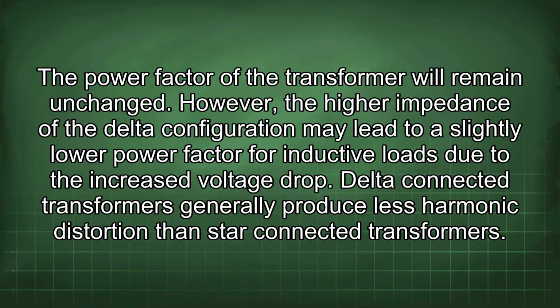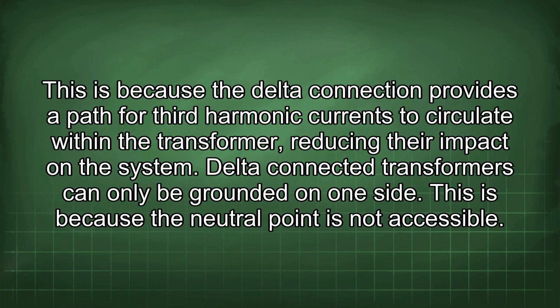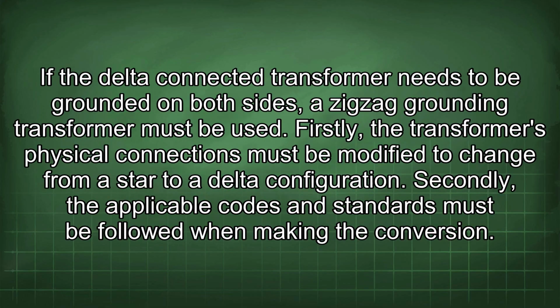Delta-connected transformers generally produce less harmonic distortion than star-connected transformers. This is because the delta connection provides a path for third harmonic currents to circulate within the transformer, reducing their impact on the system. Delta-connected transformers can only be grounded on one side. This is because the neutral point is not accessible. If the delta-connected transformer needs to be grounded on both sides, a zigzag grounding transformer must be used.